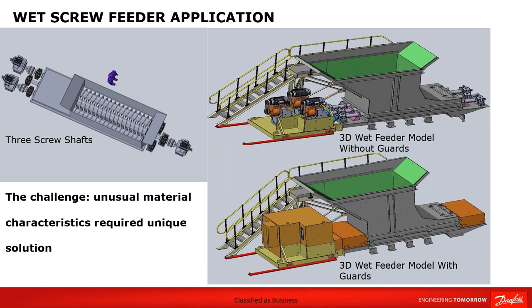The final application setup comprises three screws connected to the 22 kilowatt motors and reducing gearboxes. The master, or the center motor, is attached to a Danfoss VLT FC302 automation drive with a Profibus, and here we did use encoder options. The Profibus master is the plant control system controlling the operation speed of the motor according to process requirements, and the master motor is fitted with an encoder to increase its dynamic torque response. And the shaft of this motor has a reference encoder to measure the actual screw shaft rotational speed.